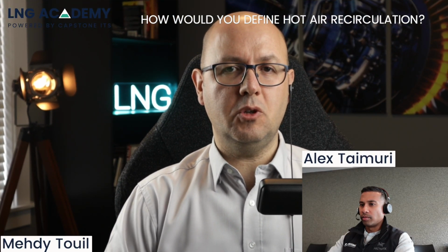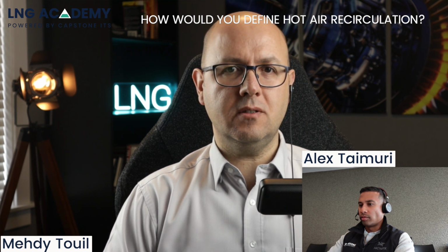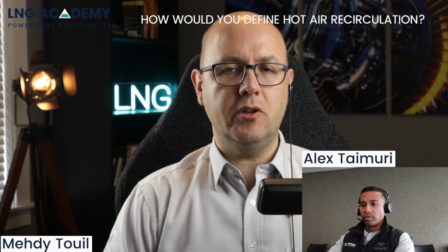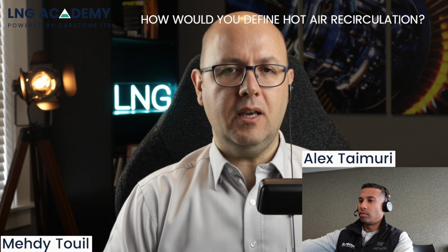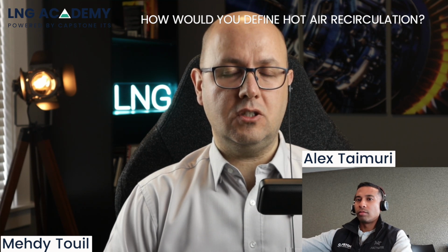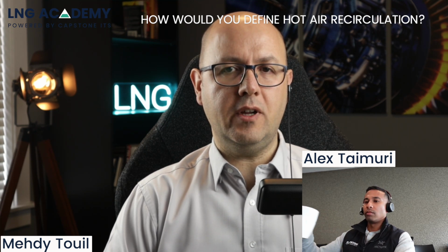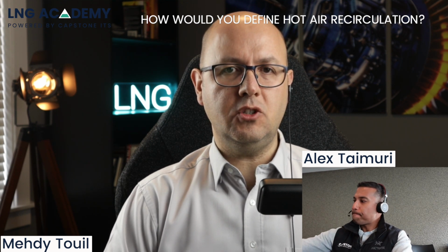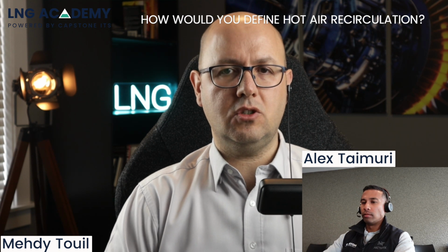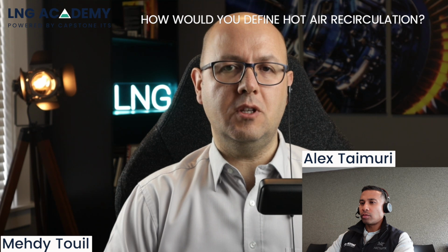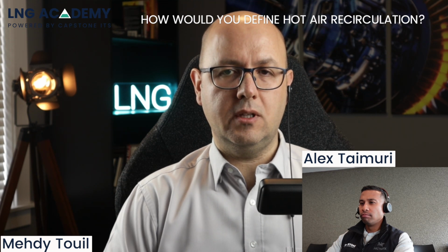Thank you, Alex. So most LNG trains are designed with a pipe rack located in the facility center, flanked by compressors, cooling heat exchangers, and other pieces of equipment for processing and liquefying natural gas. The air-cooled heat exchangers use large axial flow fans to move air across finned tubes, which results in the elimination of heat and/or the condensation of the processed gas. Hot air recirculation is a well-documented phenomenon that affects air-cooled LNG plants.